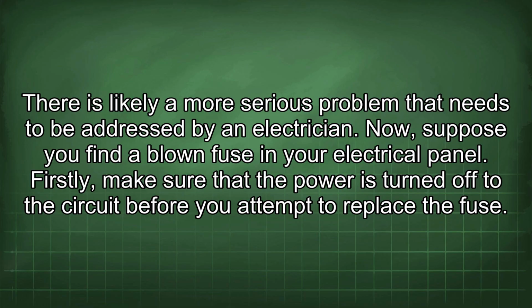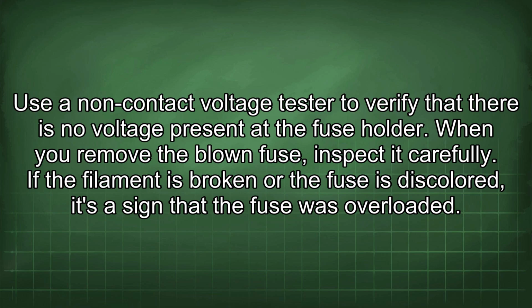Now, suppose you find a blown fuse in your electrical panel. Firstly, make sure that the power is turned off to the circuit before you attempt to replace the fuse. Use a non-contact voltage tester to verify that there is no voltage present at the fuse holder. When you remove the blown fuse, inspect it carefully. If the filament is broken or the fuse is discolored, it's a sign that the fuse was overloaded.